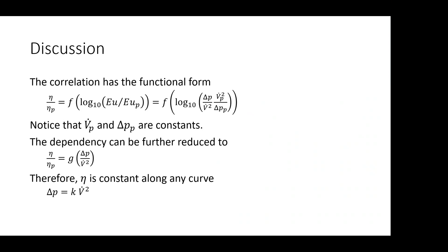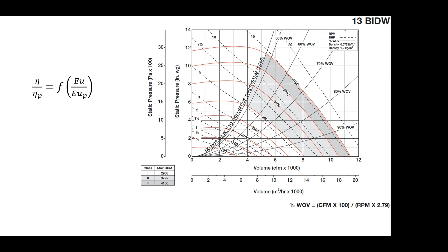But fortunately for us in the United States, this is in line with the simplification often used by fan and pump manufacturers, which is explicitly permitted by ASHRAE Standard 51. So what this means is that if we look at this fan power map, it kind of claims it tested multiple speeds, but it actually only tested one of them. All the other curves are just scaled down. If we find any curve that's a constant system curve, the efficiency at these points is all the same. So it looks like they tested a lot, but not really. Therefore, it is safe to say that this implemented method has the same accuracy as using manufacturer data you would find in this country.